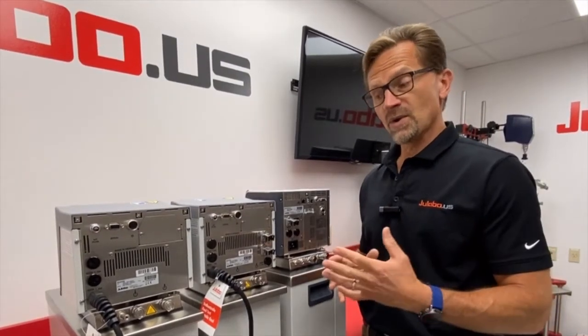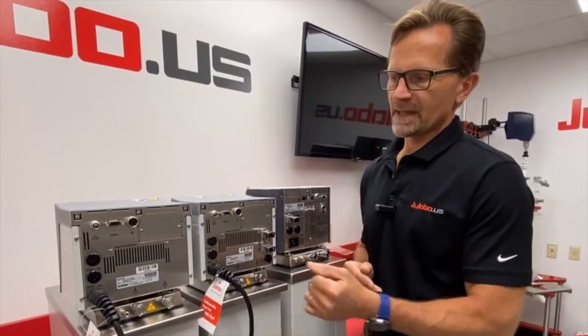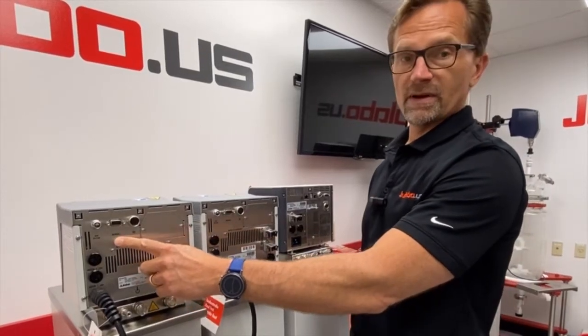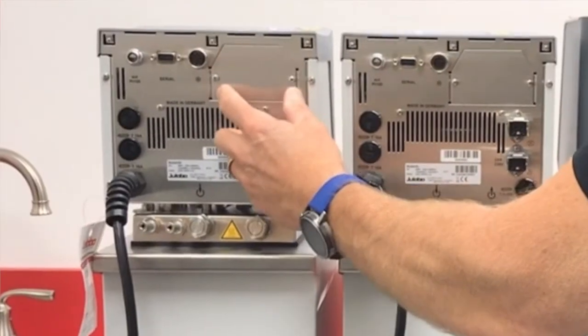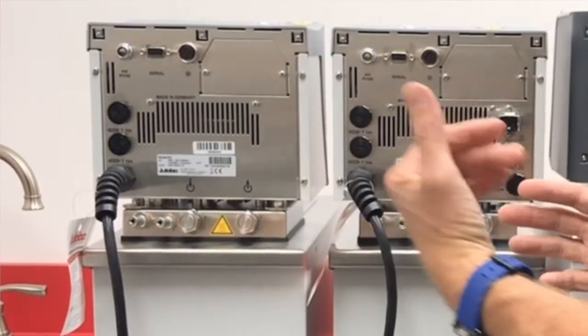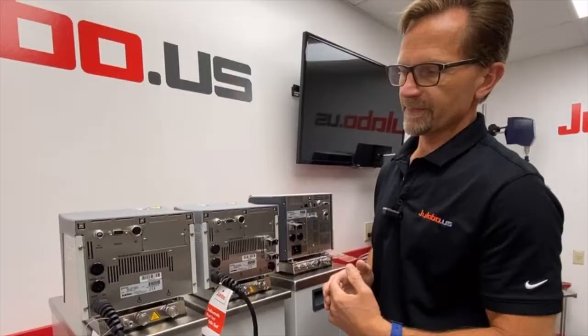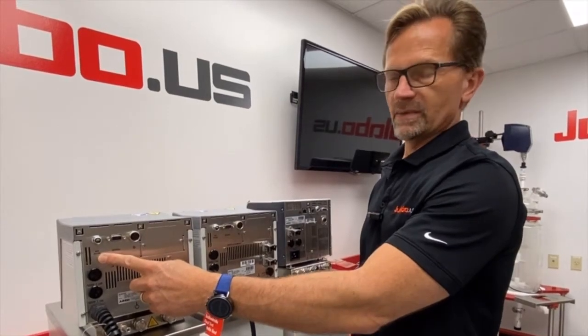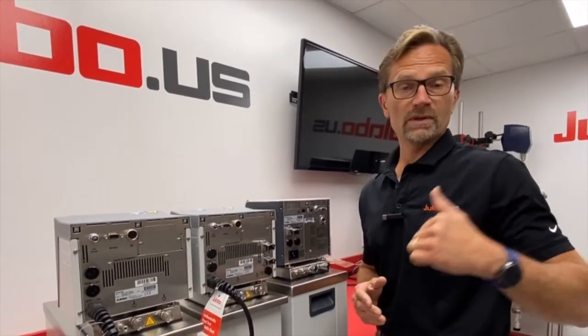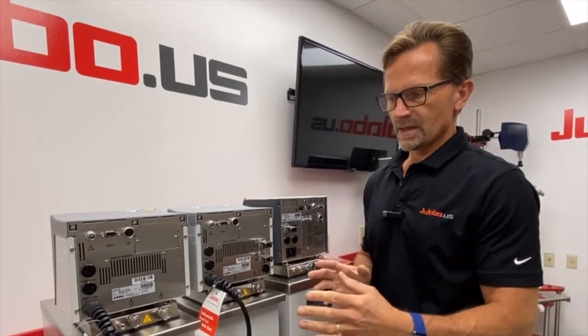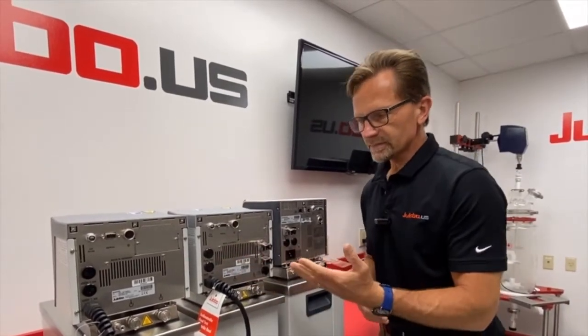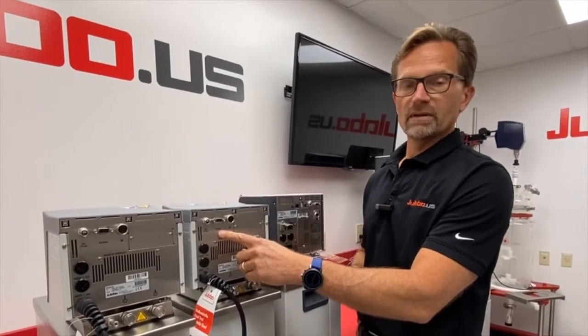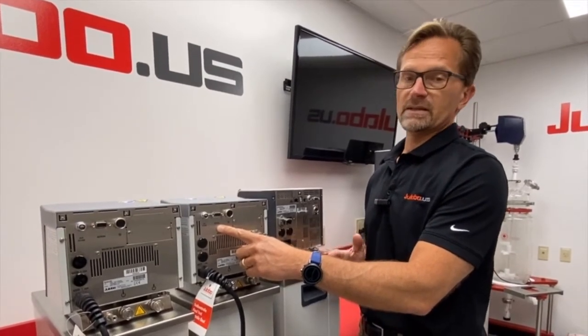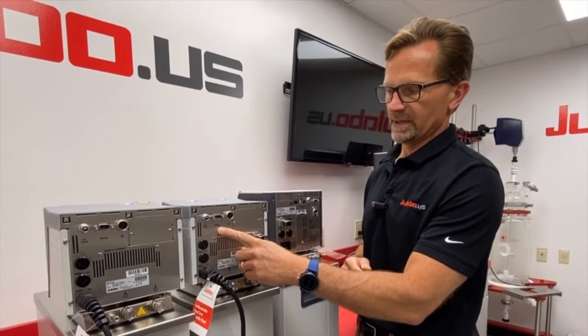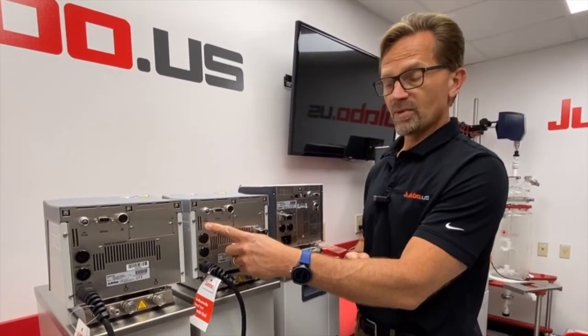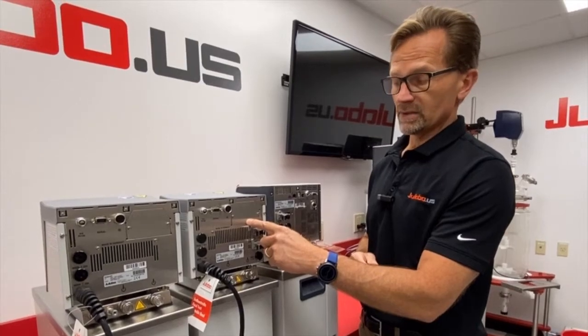So let's look at the I/O on the models to do a comparison. On the SE, we have a serial port for RS-232 and an optional slot here for an analog module if you want to control via voltage or current. There is also an external PT100 port, which is important for controlling from your external application. If we move on to the SL model, you'll see we also have a serial port for RS-232, but the SL also adds RS-485 capability. We still have the PT100 port and the optional analog module slot.